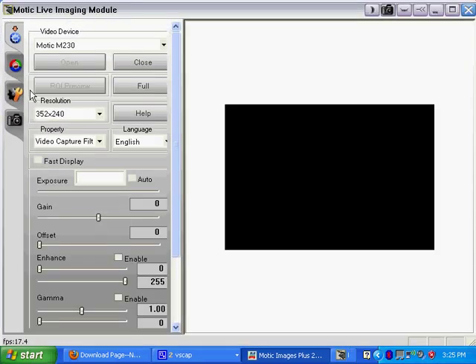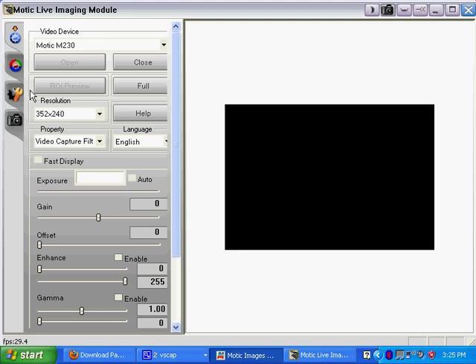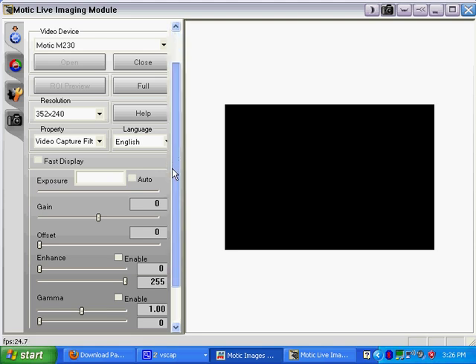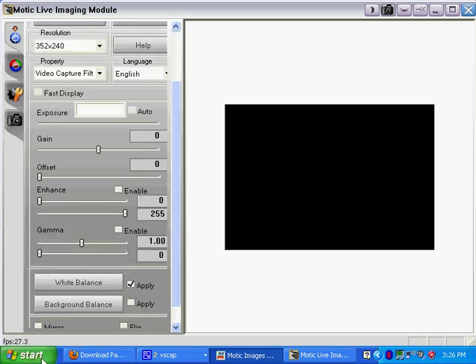Right now, as you can see, I have a black screen. That's nothing to worry about. How to know that your camera or microscope is connected to your software is under video devices. It does show something in this box. For me, it would be Motic M230. For people with Moticams, it will say Motic 2.0 MP or 3.0 MP. As long as it says something, you know your camera is connected to your software. Another thing to check out is your FPS. If there is anything here besides 0.0, your camera is most likely connected to your software.